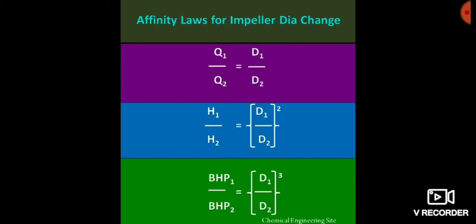The second one is the pressure relationship with the diameter of the impeller — it is a square relationship. If we increase the diameter of the impeller two times, then the pressure head increases by four times. The third one is BHP (brake horsepower): if we increase the diameter two times, then the brake horsepower will increase eight times.